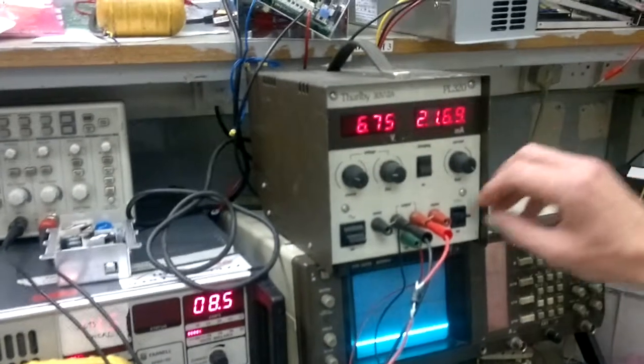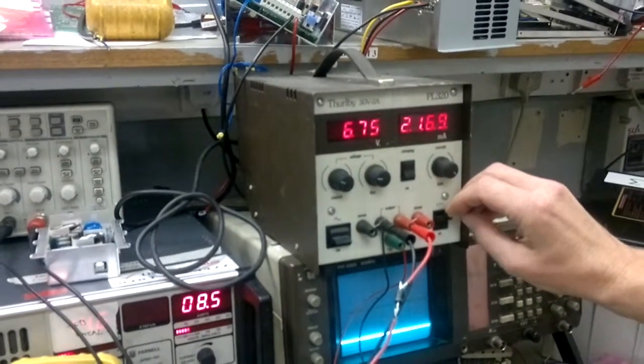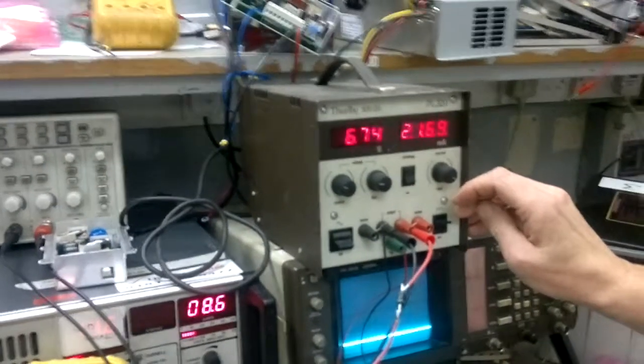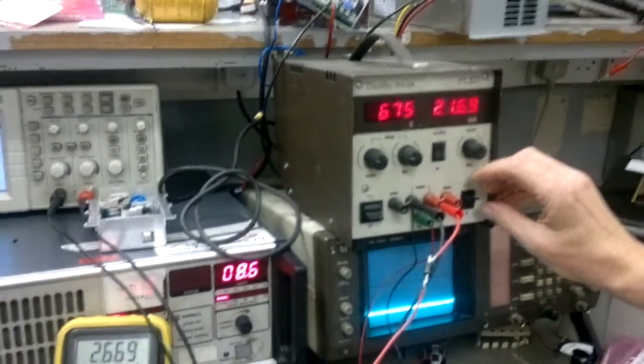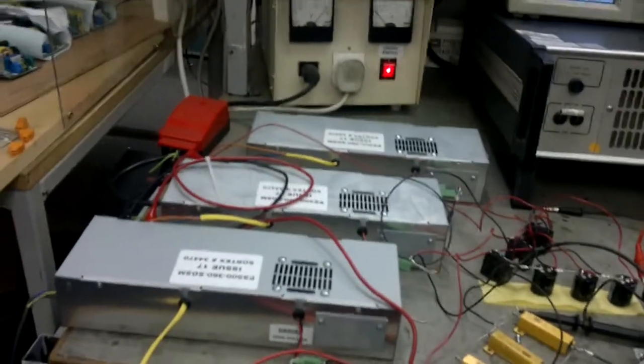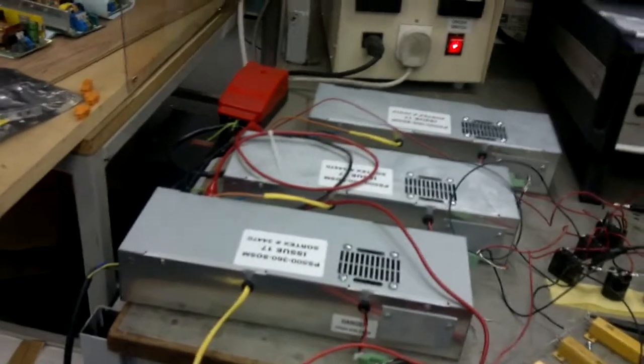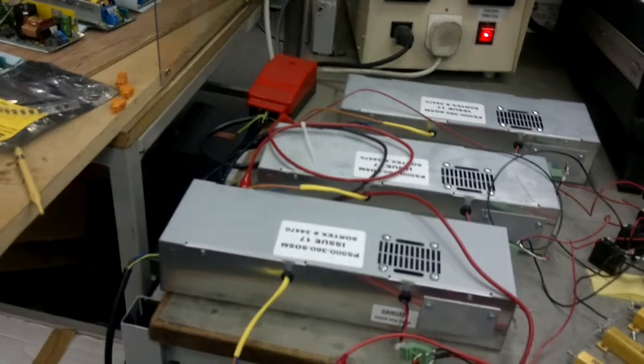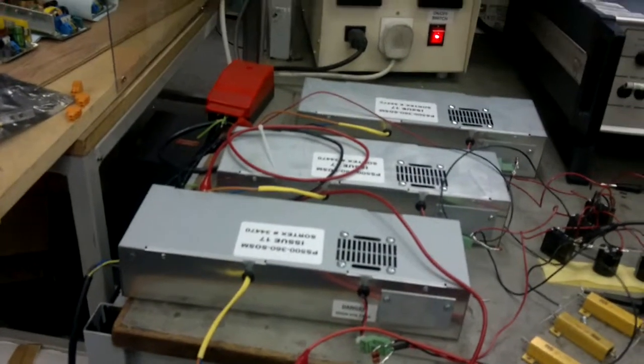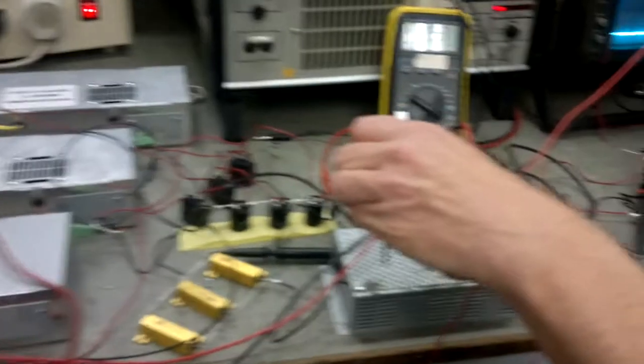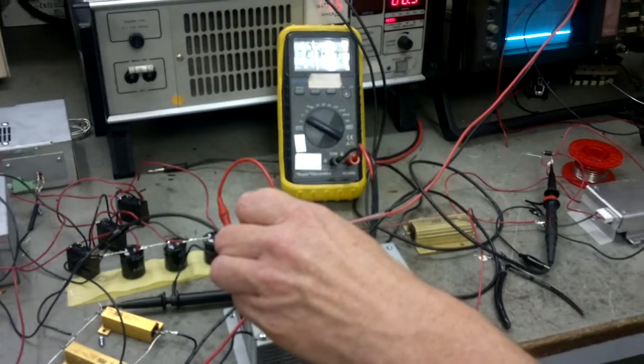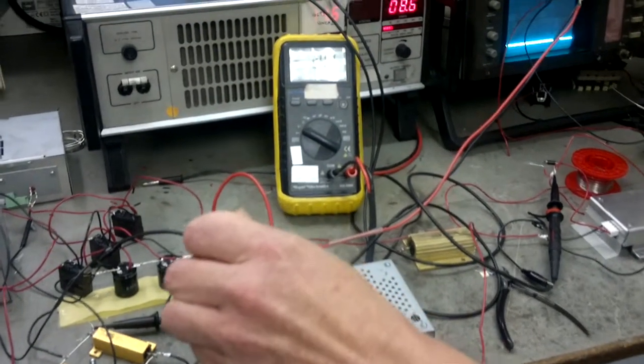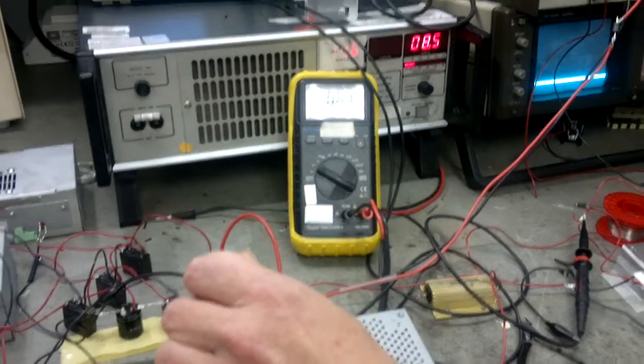When the enable is switched off, these units switch off. So to start the process, what we'll do is switch off the enable power supply, and that means that we're now ready to run a discharge from the capacitors, and here we go.